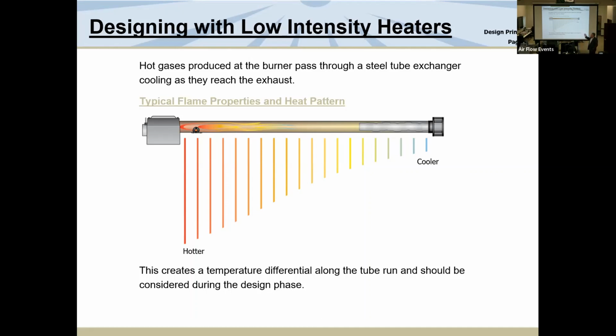The hard part with infrared heaters is, as we get further down, I am getting better efficiency values, but I'm getting very poor radiant heat. A tube temperature at the end that's only 100 degrees or 200 degrees is not emitting any radiant heat. Our body temperatures are 100 degrees. Remember, radiant heat is a function of temperature to the 4th power. So you want hot. So sometimes we compete with how the heaters are certified with this end number that we must chase versus the reality of a good radiant heater. See how this goes. I'll see how we do on time here. All right, next slide, please.